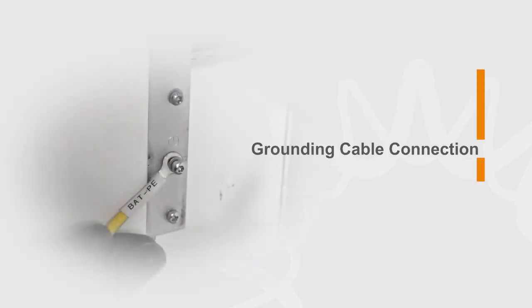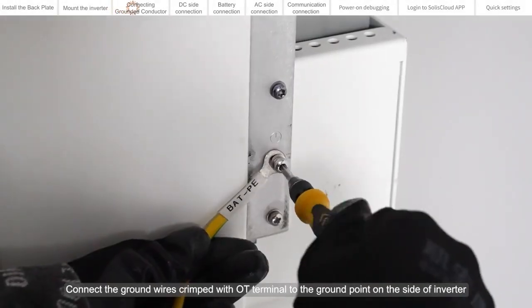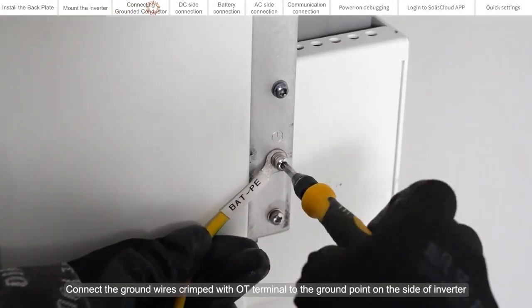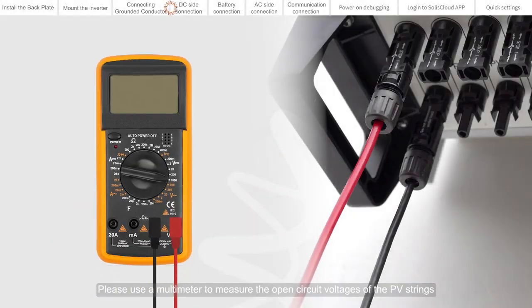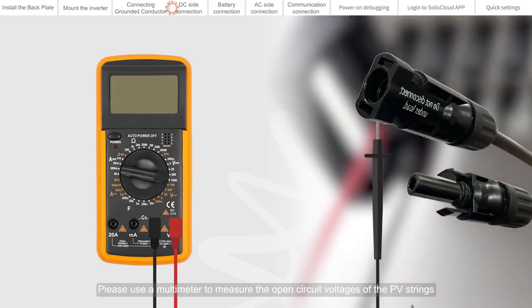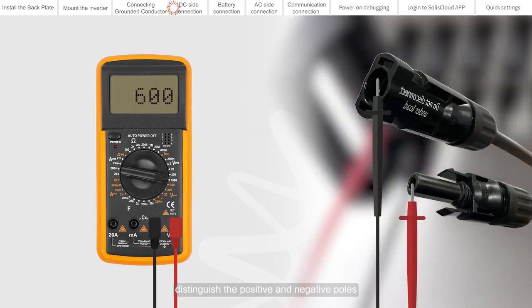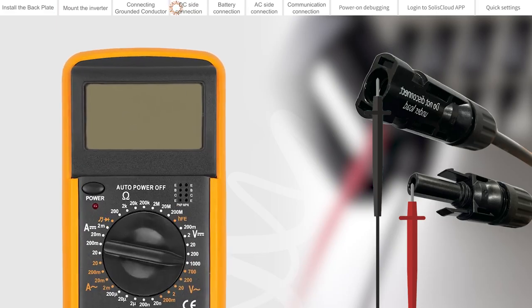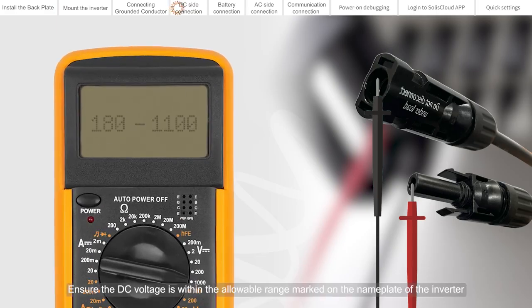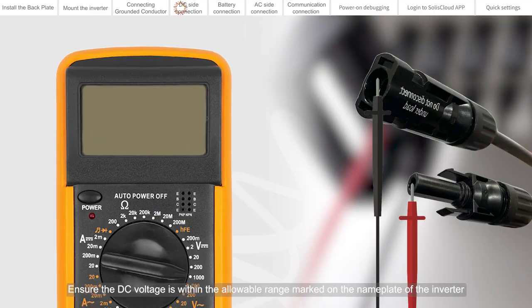Grounding cable connection. Connect the ground wires crimped with OT terminal to the ground point on the side of the inverter. DC side connection. Please use a multimeter to measure the open circuit voltage of the PV strings. Distinguish the positive and negative poles. Ensure the DC voltage is within the allowable range marked on the nameplate of the inverter.